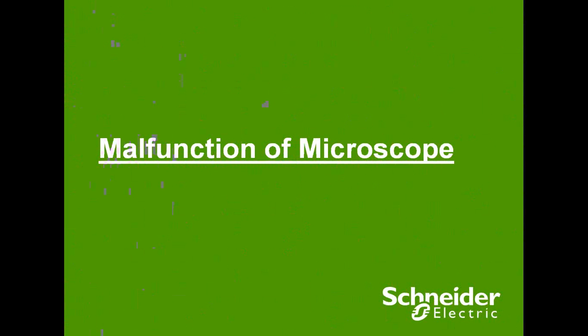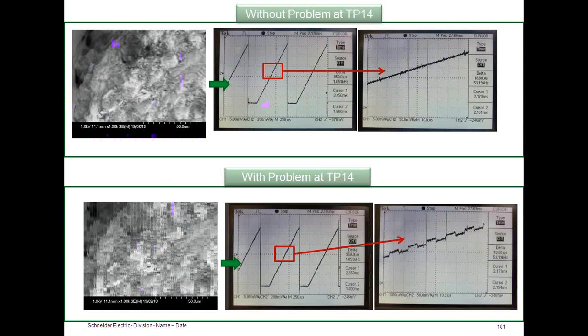Here we have an example where we have a microscope, an electron microscope used in one of the biggest FMCG companies. The top image you're seeing is the clear image, and the bottom image is hazy. It's not so clear. Both images are from the same machine, but there is a UPS feeding this microscope, and the same UPS is also feeding some computer loads. Whenever you switch on the computer loads and the microscope, you get this hazy blurred vision in the microscope. And when you switch off the computers, we get clear vision.